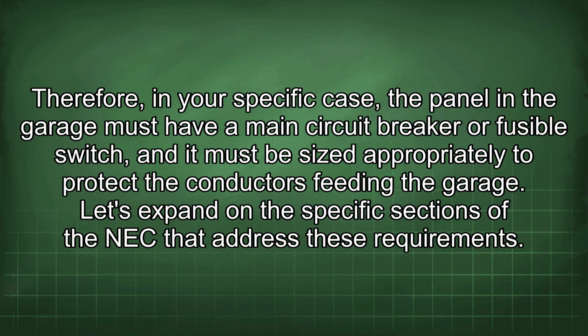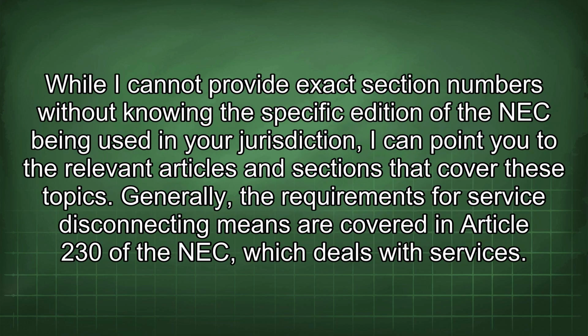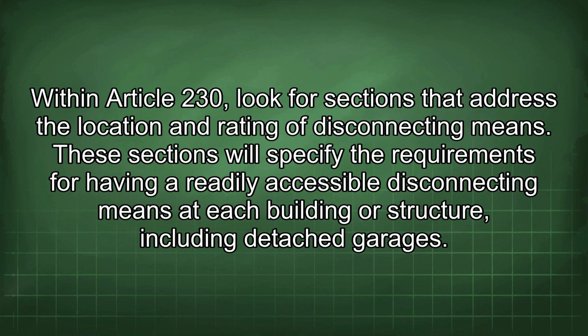Let's expand on the specific sections of the NEC that address these requirements. While I cannot provide exact section numbers without knowing the specific edition of the NEC being used in your jurisdiction, I can point you to the relevant articles and sections that cover these topics. Generally, the requirements for service disconnecting means are covered in Article 230 of the NEC, which deals with services. Within Article 230, look for sections that address the location and rating of disconnecting means. These sections will specify the requirements for having a readily accessible disconnecting means at each building or structure, including detached garages.